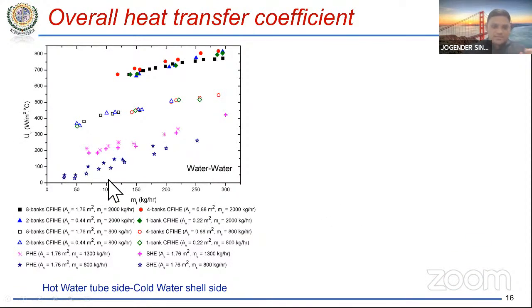I know that this slide is a little busy, but try to pay attention with me. This is the overall heat transfer coefficient on the y-axis, and this is the mass flow rate inside the tube in kg per hour, inside the tube of the heat exchanger. We try to compare the results of our device, the CFI heat exchanger, CFI HE as we are calling it, and we took different banks: 8 bank, 4 bank, 2 bank, and 1 bank. The surface area for the 8 bank heat exchanger is 1.76 meters square. For the 4 bank heat exchanger, the surface area is just half of that, 0.88 meters square. For 2 bank, it is 0.44 meters square. For 1 bank, it is 0.22 meters square.